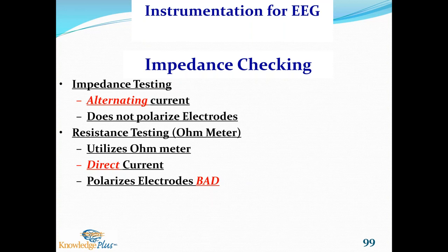Now, every time you do an impedance check, it charges the electrode, puts a different charge in the metal. But with alternating current, it charges it and takes it back. It doesn't polarize the electrodes. With resistance testing, that's using an ohm meter, that uses direct current, and that polarizes the electrode. That's bad.